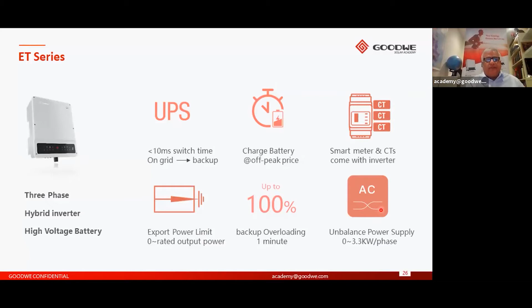Colin will probably touch on this later, but this is one scenario that you can use for the ET. They can be paralleled. So in this example, if you have 100 kilowatts on the roof, you can have 10 of these 10 kilowatt ET units, all with their own individual bank of batteries, totaling, in this example, up to 100 kilowatts. So there's a lot of battery storage there. They're controlled by a separate device called a SEC 1000 hybrid. Basically, it controls all of these units connected in parallel so they work in unison, and they all charge and discharge at the same time.